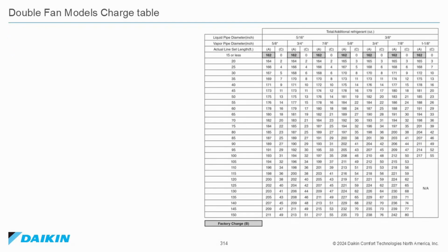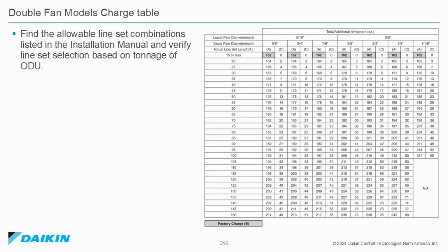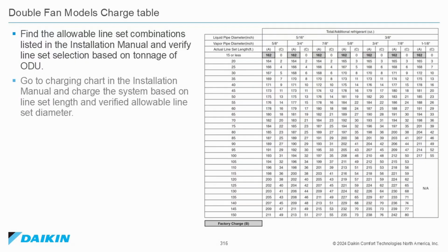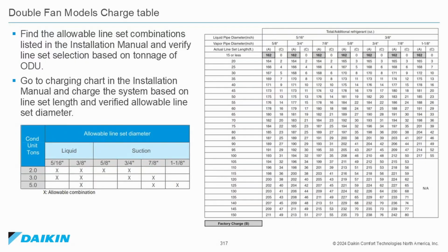Double fan model charging table is shown on the right. Find the allowable line set combinations listed in the installation manual and verify the line set selection based on the tonnage of the outdoor unit. Go to the charging chart in the installation manual and charge the system based on the line set length and verified allowable line set diameter. This chart shows the allowable combinations of liquid and suction line for 2-ton, 3-ton, and 5-ton systems.